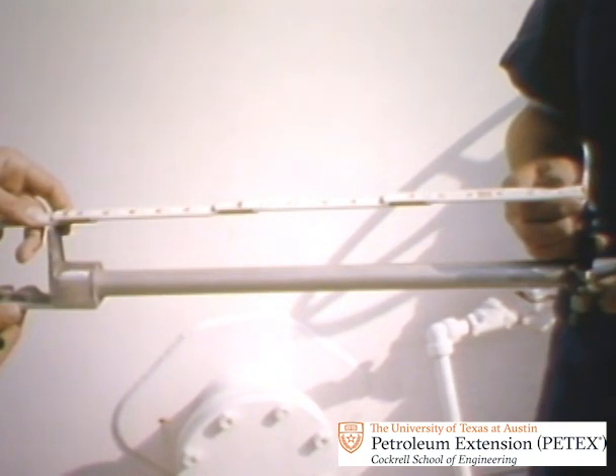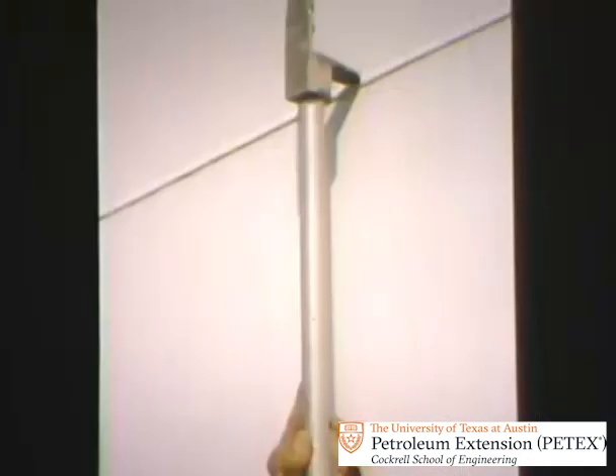To mark the tape path, first the crew takes a special pole called a strapping pole and measures the 20% distance on it, 19 inches in this case. There are no obstructions at the 20% height on this tank. The top of the pole goes on the top of the ring. A marking chalk secured 19 inches down on the pole marks the shell at the proper distance for the tape path.